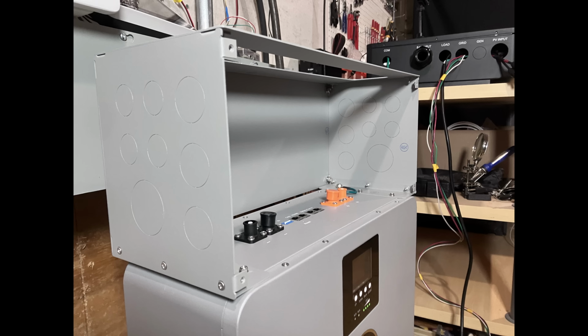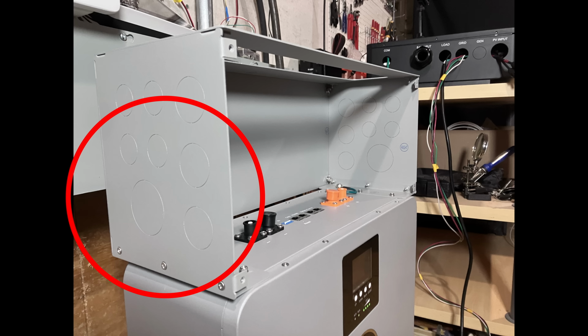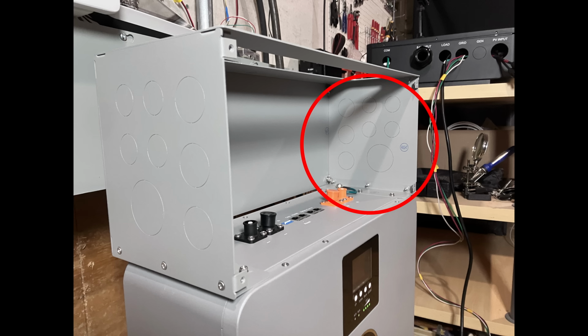So after I got the conduit box all put together, it looks like the knockouts on the left side and the right side don't match. That's not a big deal if you're only using one wall mount battery, but if you're looking to parallel multiples together, the larger knockouts won't line up. The 3/4 inch ones still do. I made EG4 aware of this, and they're working on resolving the issue.